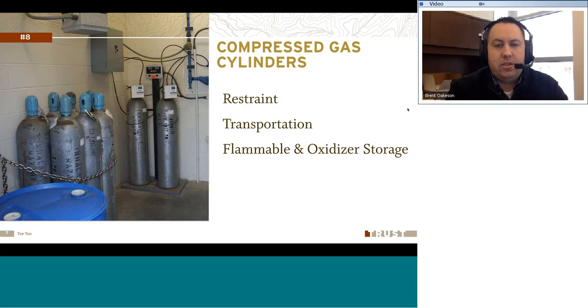One thing to watch for is your separation of oxygen and acetylene bottles. We see this sometimes. They're stored in the same areas, and they're obviously something that you want to take some real caution with. They recommend that you have these at least 20 feet apart or separated by a fire-rated barrier. So recognize that in your workshops and different places you have the cylinders. Keep those things separated, keep them chained up and restrained.